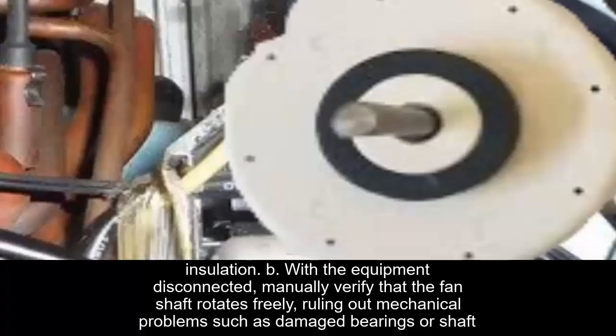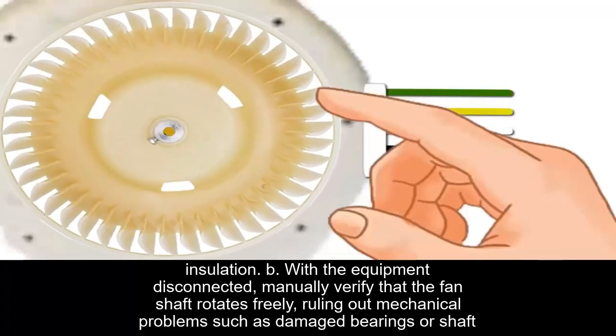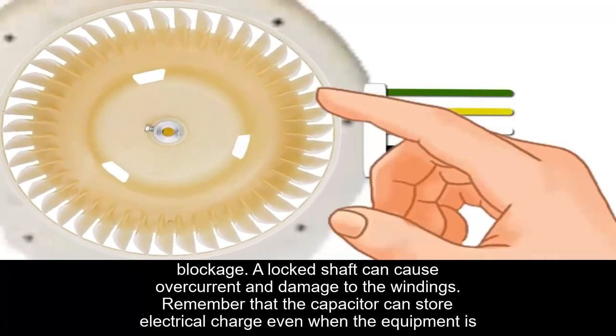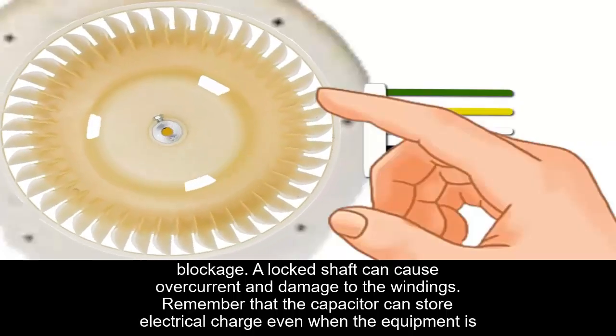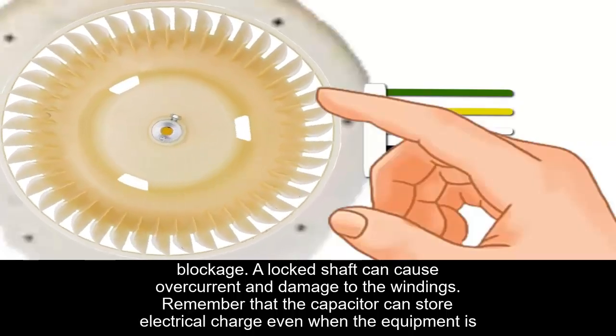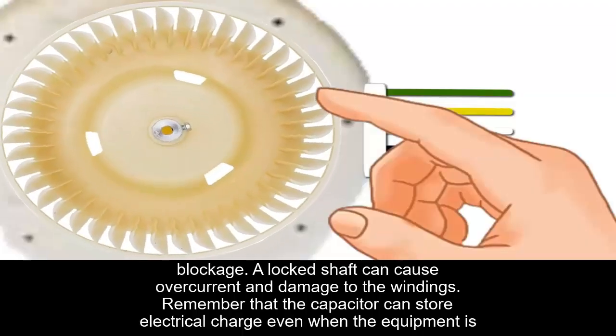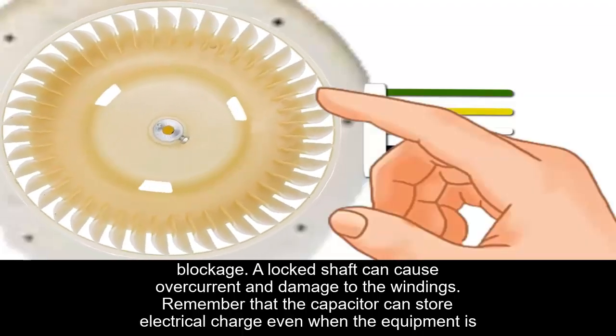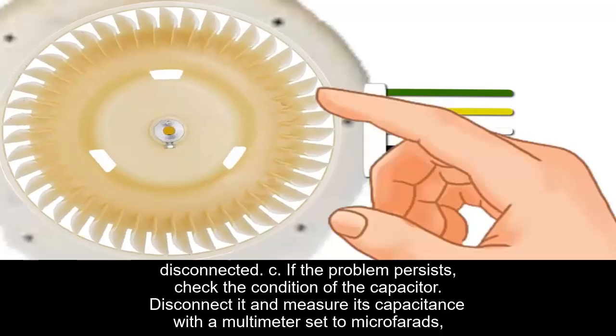B. With the equipment disconnected, manually verify that the fan shaft rotates freely, ruling out mechanical problems such as damaged bearings or shaft blockage. A locked shaft can cause overcurrent and damage to the windings. Remember that the capacitor can store electrical charge even when the equipment is disconnected.